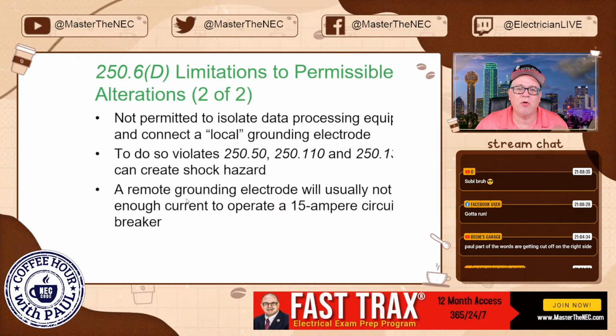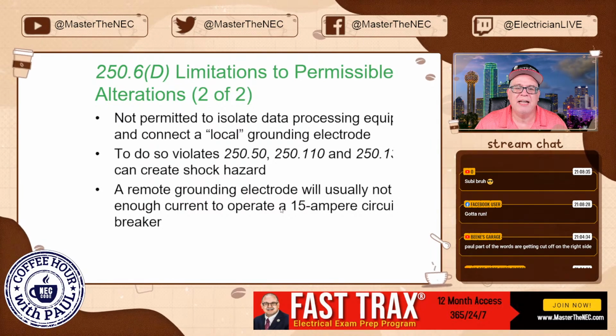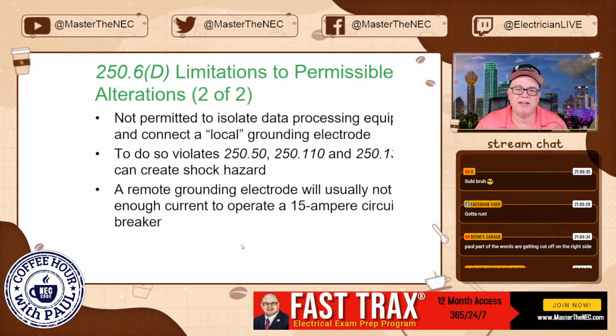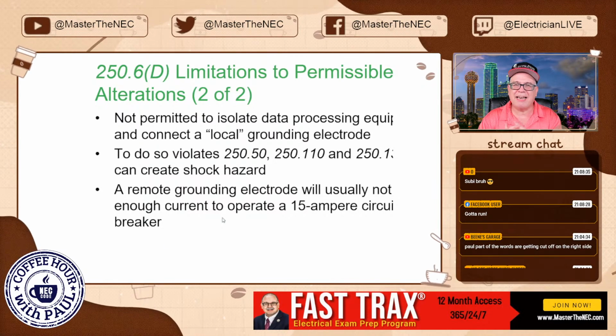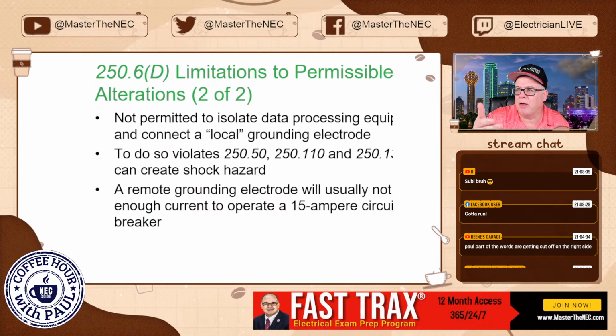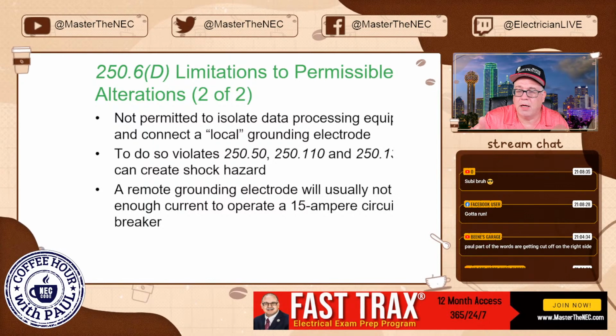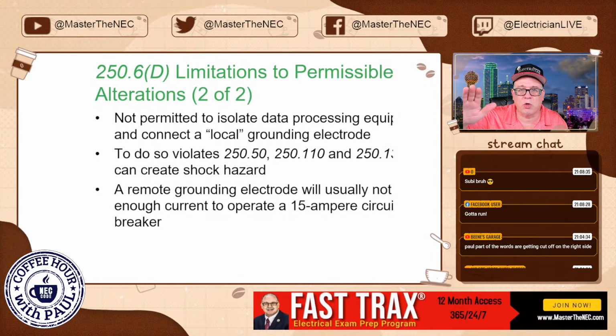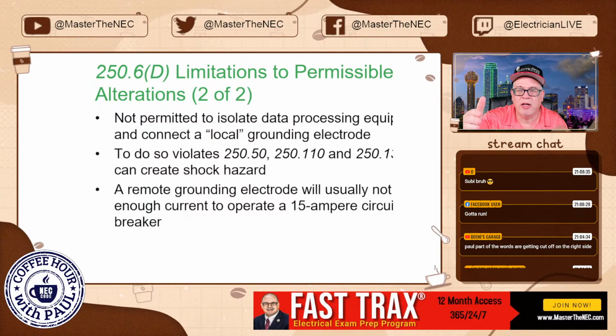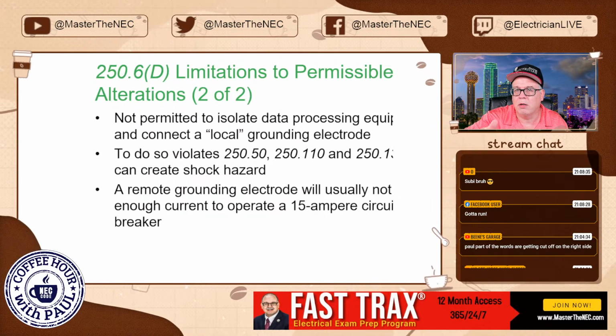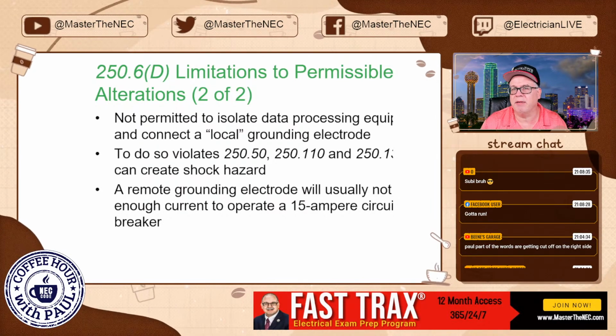Now, it says a remote grounding electrode will usually not carry enough current to operate a 15 amp circuit breaker. We already kind of did this, and then we used the example of a light pole, right? If it's a perfect ground rod in a perfect world, 25 ohms, 120 volts, you do the Ohm's law. What do you think the amps are going to be?